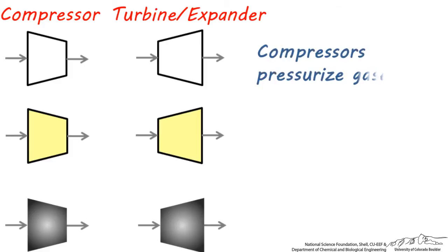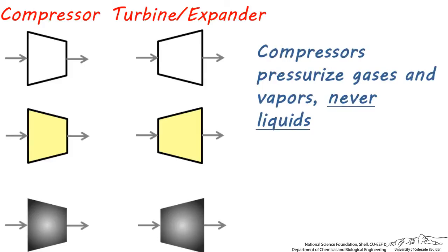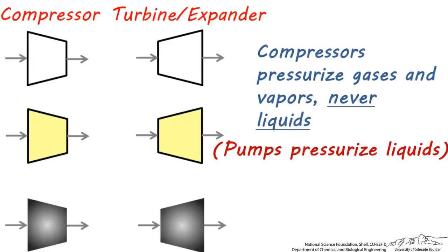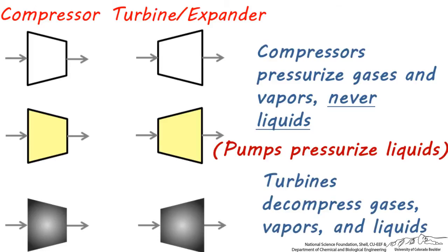It's important to remember that compressors only compress gases and vapors. Compressors are very expensive pieces of equipment, and sending a liquid through them will damage the rotors and stators. Remember that pumps are what we use to pressurize liquids. Turbines, on the other hand, decompress gases, vapors, and liquids.